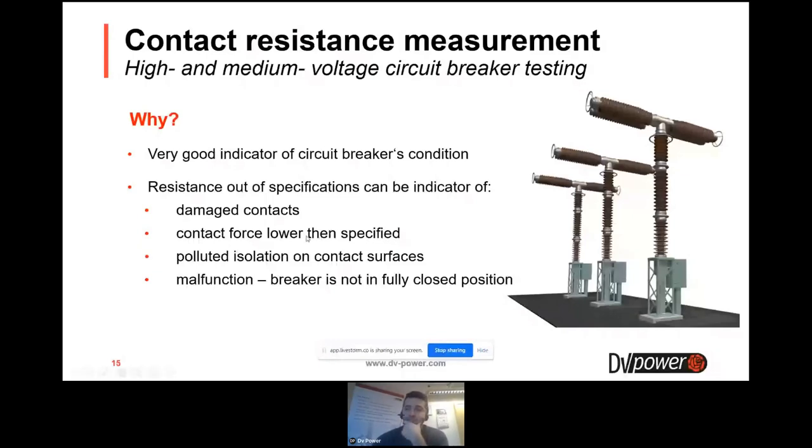And usually these kinds of faults are main faults, because they occur inside the contact chamber, so you cannot disassemble the contact chamber easily. So if you have this kind of fault, then you have a huge problem. But of course, before saying that you have a problem, you need to check in detail. And the last solution is that the circuit breaker is malfunctioning.